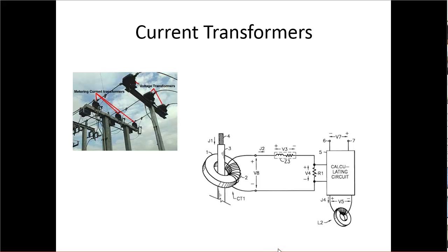What you'll see, I've got a little picture here, hopefully you can see this okay, but we've got the instrumentation that's on the lines. In order to measure the current, you use something called a current transformer, or a CT, and to measure the voltage, you use a voltage or a potential transformer, a PT. You'll hear distribution engineers will talk about CTs and PTs a lot, and this is just simply the instrumentation that they're putting on the lines.